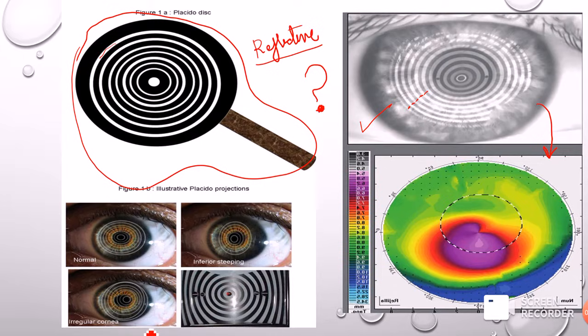The software studies the spacing between the rings: wherever the distance between rings is less — meaning the rings are more crowded — that part of the cornea is steeper. Wherever the distance is more, that part of the cornea is flatter or less curved. Using mathematical algorithms, the software converts that ring spacing into dimensions to generate a map that tells you about the anterior surface of the cornea.